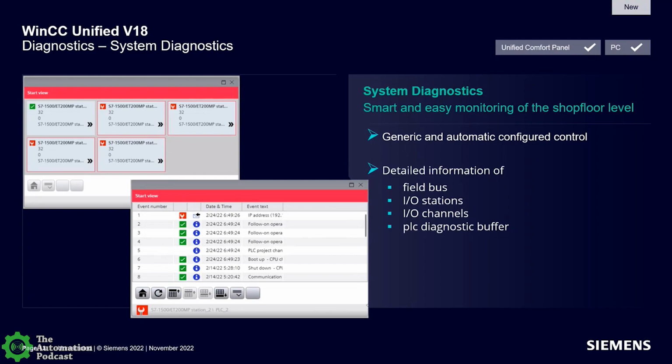Yeah, and I think I should probably, just for the Allen Bradley users out there, say it's pretty unique, because when you're running the simulated PLC, it's pretty much taking the place of the real PLC as far as TIA Portal's concerned. So the HMI just connects directly to the simulated PLC. But if you close down the simulated PLC, PLC Sim, and then you launch the HMI, it's going to connect directly to the PLC in the field.